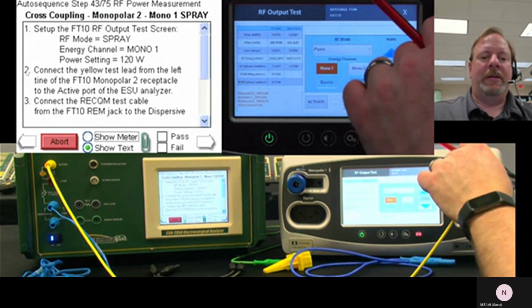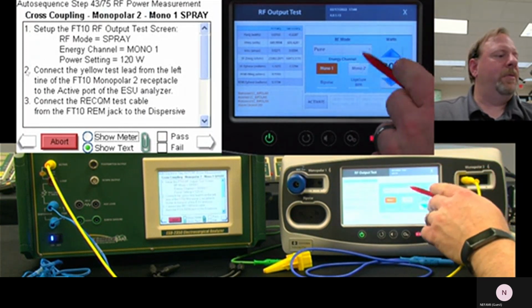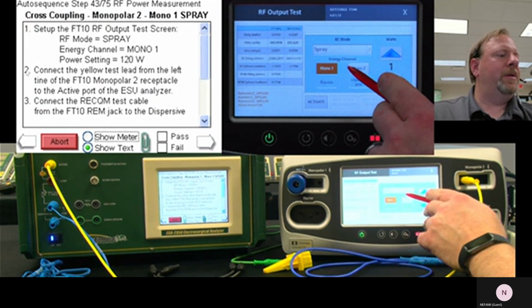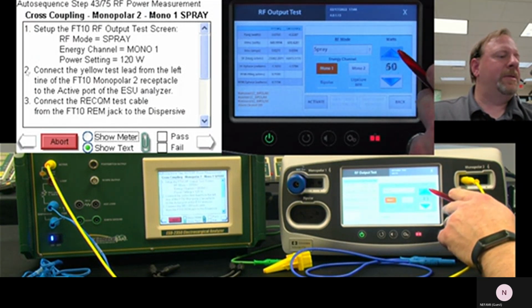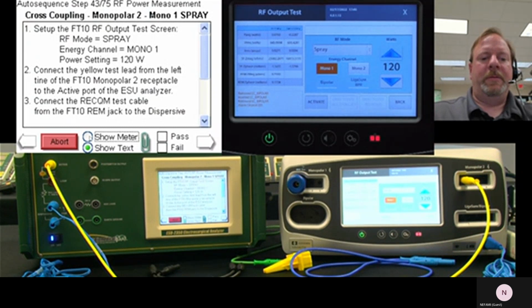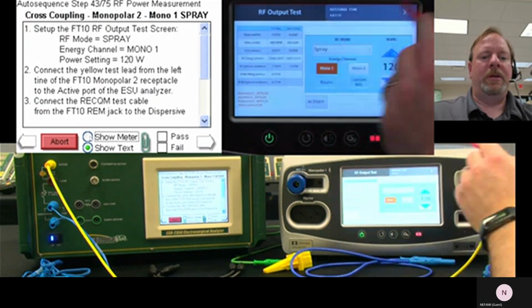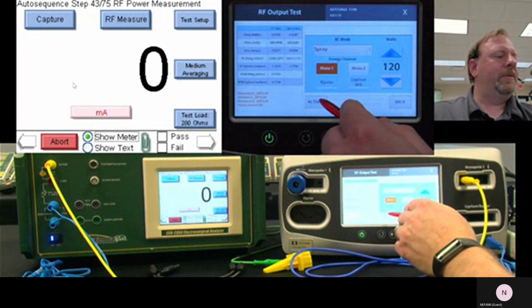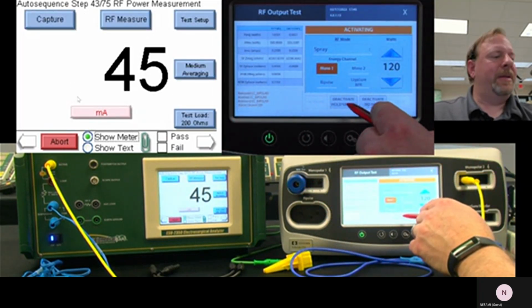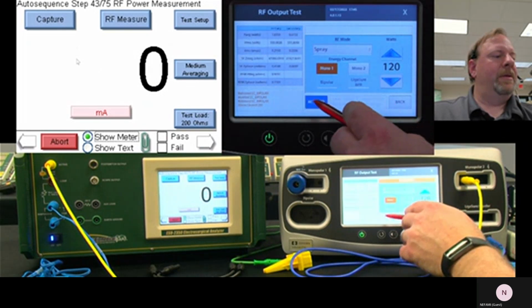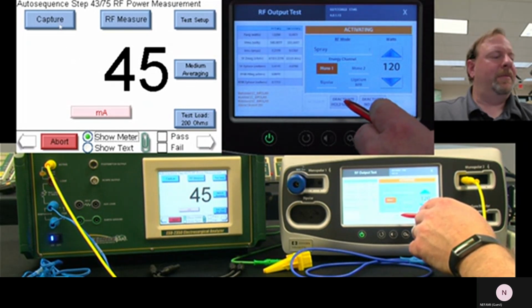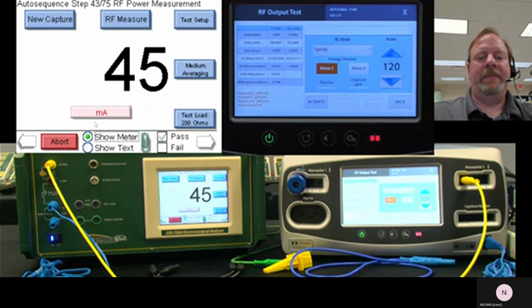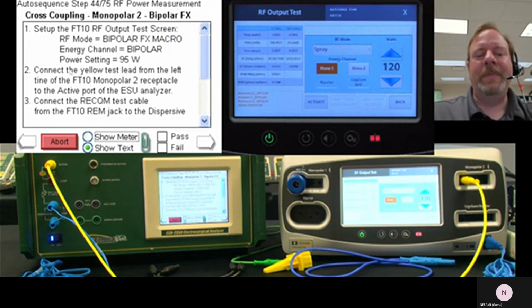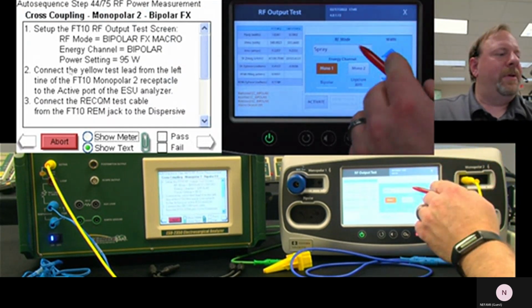Now we're going to stay connected to monopolar 2, and we did pure, now we do spray. Both waveforms, worst case scenario, maximum wattage. And show meter. We're still activating monopolar 1, connected to monopolar 2. I always like to double check that every time. I always also like to press the capture button every time. That helps. Okay, so now we're moving on.